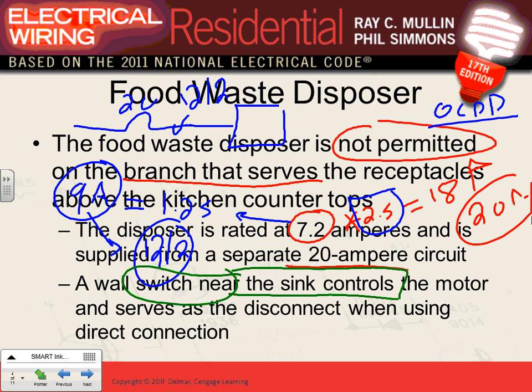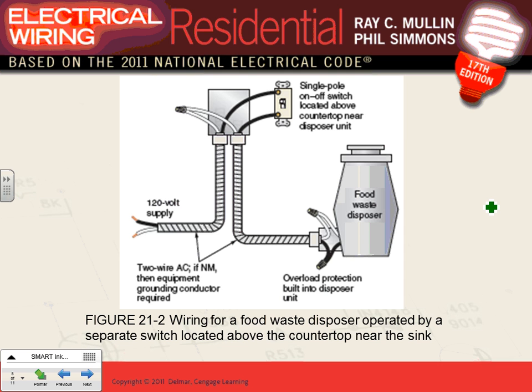If it's plugged in, then what's the disconnect? The plug is going to be the disconnect. Can I have a thumbs up, Chad? We understand why this switch is there? Okay. So that's basically what they have with this garbage disposal. Piece of cake, huh? Here's how it looks. So this is where we brought, guys, our 20 amp circuit here, and we brought our neutral here, and there are two functions for this switch in this case. Number one, disconnect for the appliances, and number two, a controller.